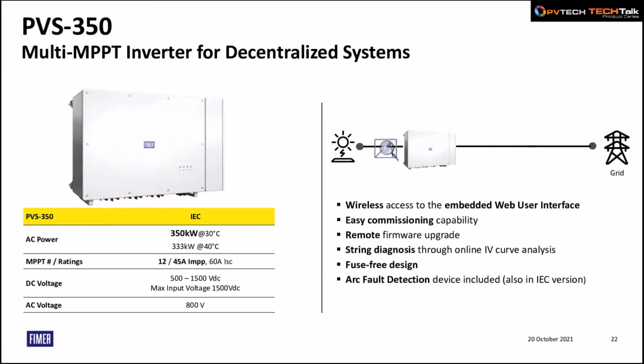In a nutshell, let me summarize some of the key numbers, key figures of the product. The inverter PVS350 is able to deliver up to 350 kilowatt at 30 degrees, slightly derated to 333 at 40 degrees ambient. Very important is the 12 MPPTs, which we have introduced in this new generation with 45 amps, so that we are enabling the connection of the new ultra high power module.